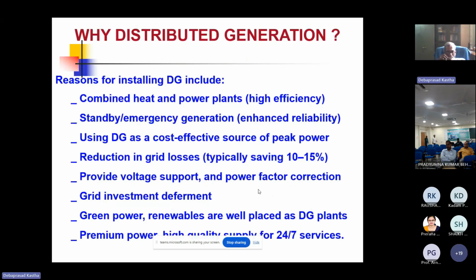So the main reasons for interest in DGs are as follows. You can have combined heat and power plants, particularly for captive generation. Standby emergency generation for emergency situations like in hospitals. Using DG as a cost-effective source of peak power. If you have a limit on peak power and draw more than that from the utility, you will have to pay a penalty. That can be mitigated using DG.